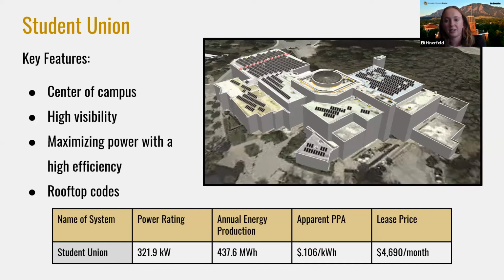This combination allows for great visibility of the solar installations. Our goal with this system was to maximize the power output while also keeping relatively high efficiency, which is the reason for the different tilted and angled solar panels on each of the roofs. The main reason some of the roofs don't have solar panels is due to sizing. With the fire codes for perimeter walkways and spacing of panels, we could only use the larger rooftops.